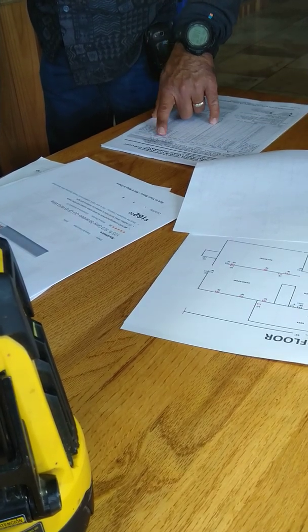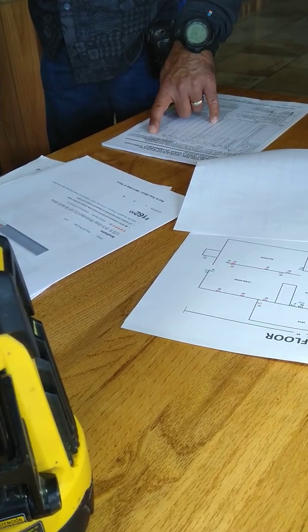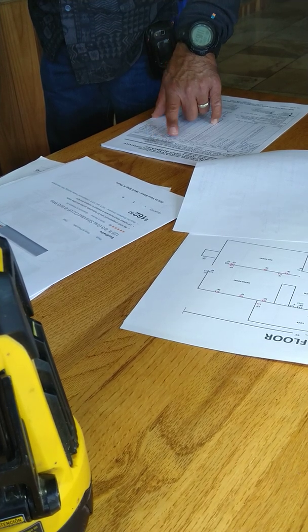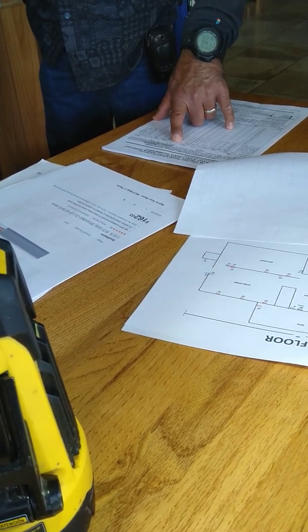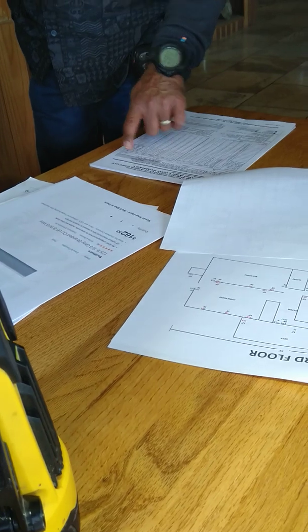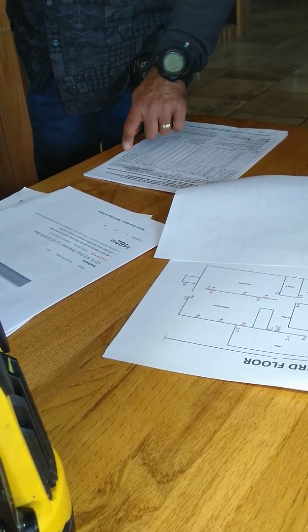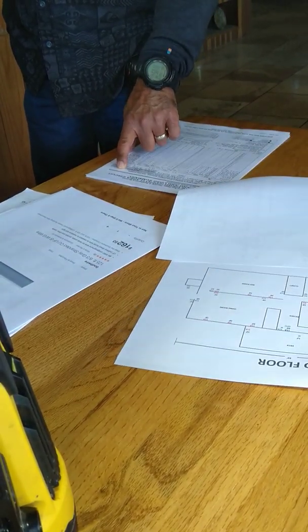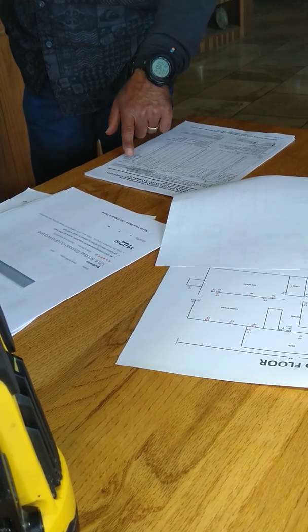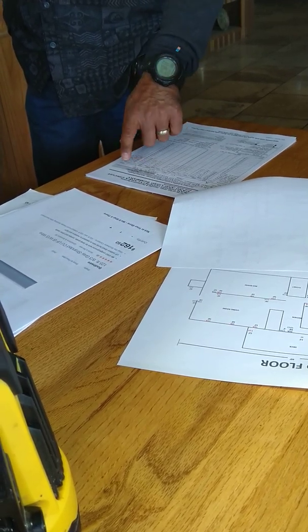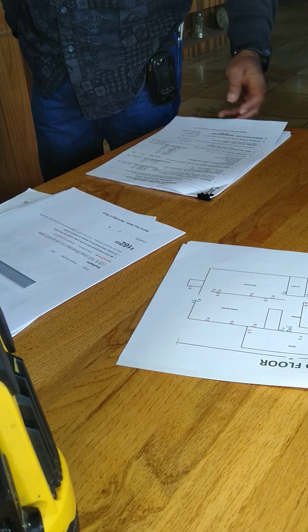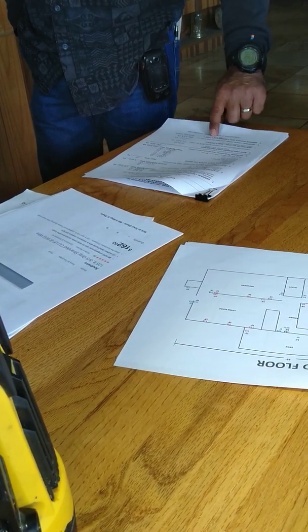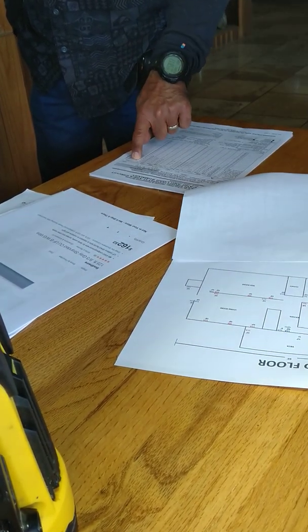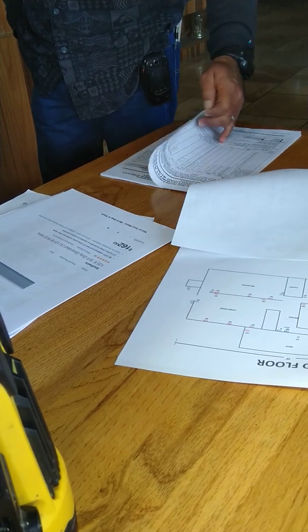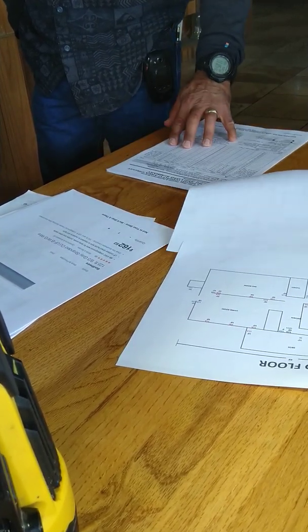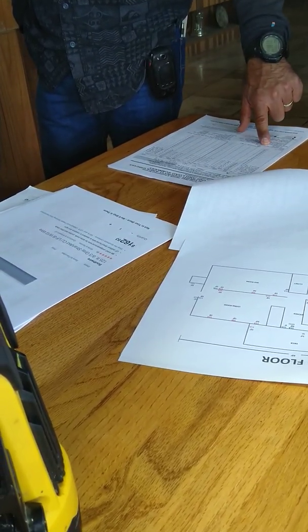This is the feeder size, and here you have a single phase. That's what that stands for. So it's a single phase, 120 volts. It doesn't say anything about amps, so you could pencil something in over here to say amperage. So you're tallying this up, and you're coming up with this number here, your total load for this particular sub panel. Each one would be done that way, and that way you know the size of your feeder.